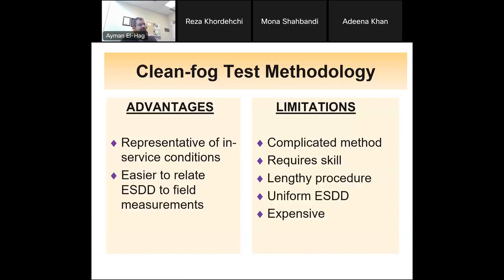Now, what are the advantages and disadvantages of this method? This is more representative of the field, because this is what's happening in the field. You have deposit of the pollutant on the surface of the insulators, and then whenever there is some moisture, whenever there is some wetting, you might have a flashover. It is much easier to relate to the ESDD than the salt fog test.